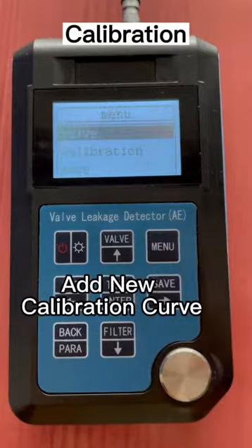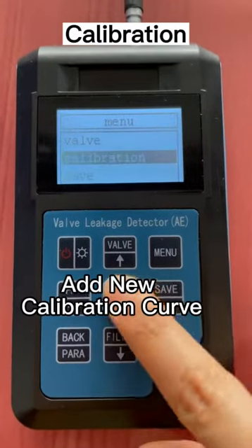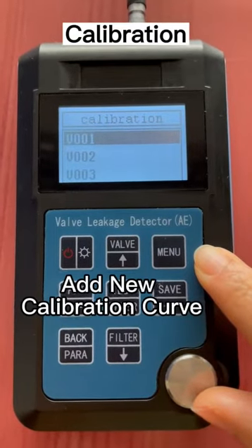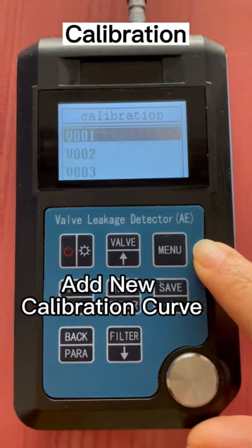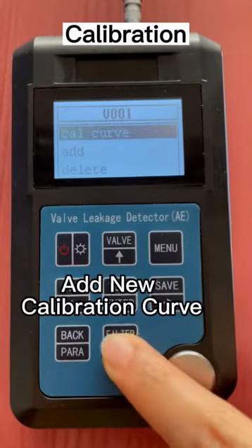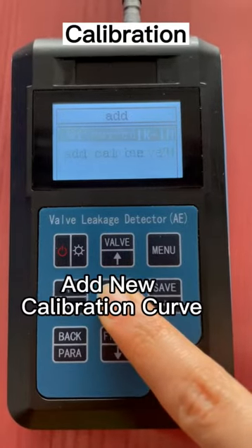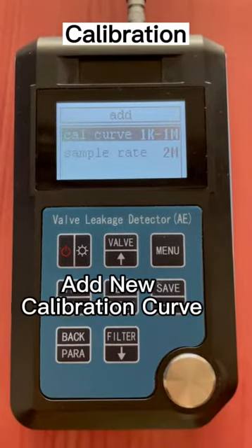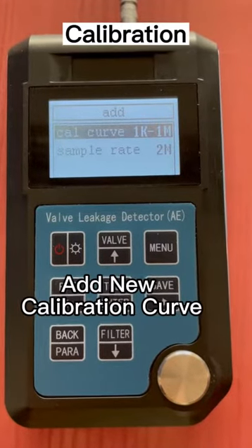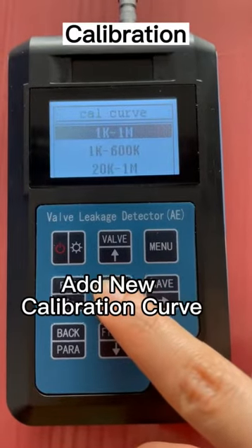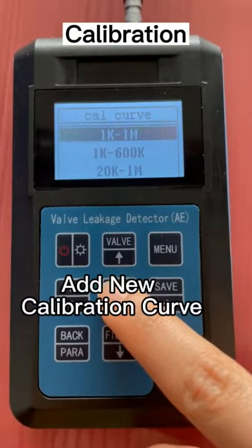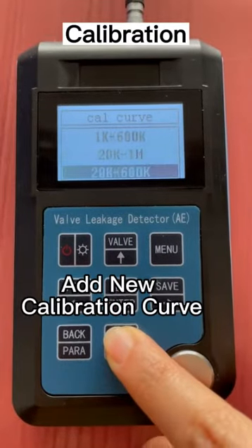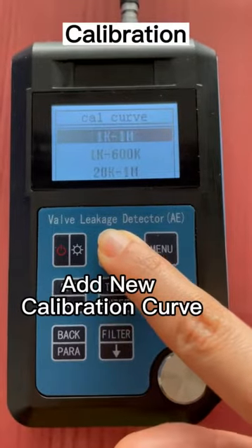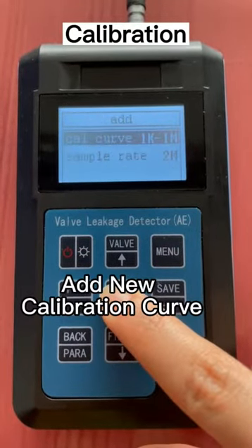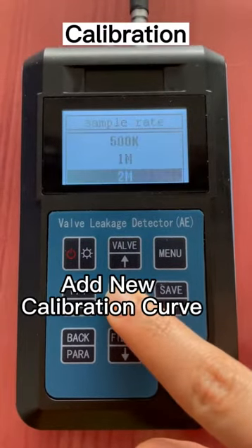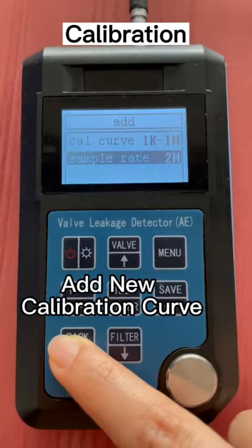Press the menu key and select calibration. Select the desired valve number, for example V001, and select Add. Press Enter. Now you need to choose the filter and sample rate of the calibration curve. Press Enter to get into the selection options. Move up or down to choose your desired range. Press Enter to confirm your selection. Press the back key to exit the page.